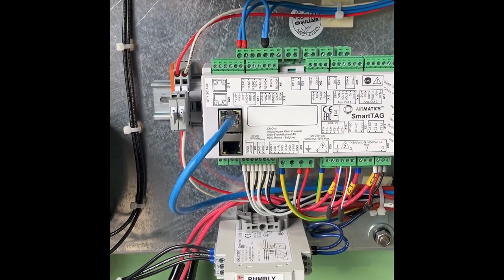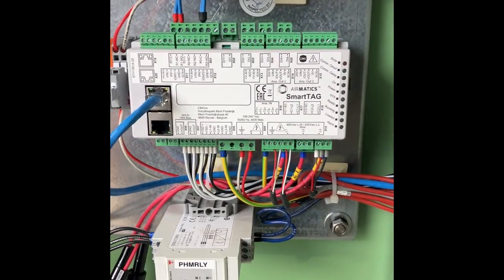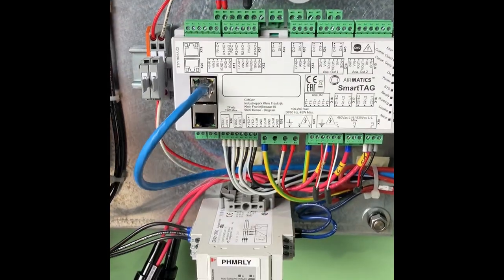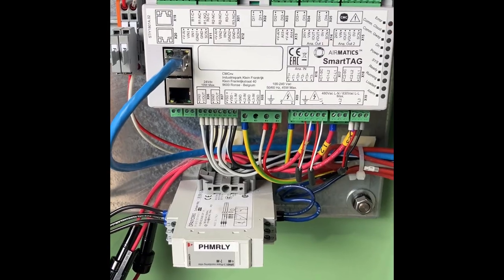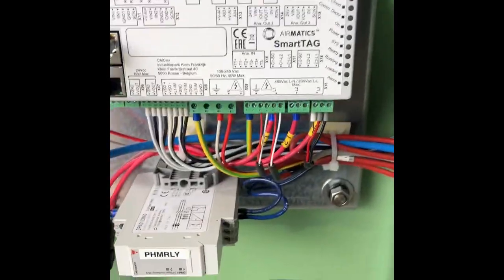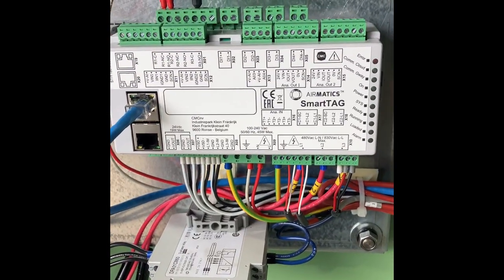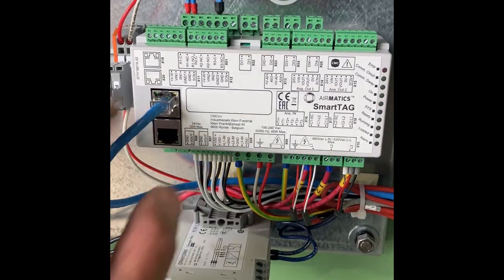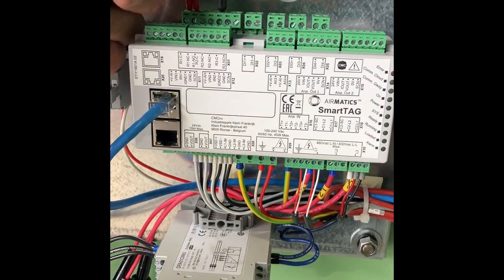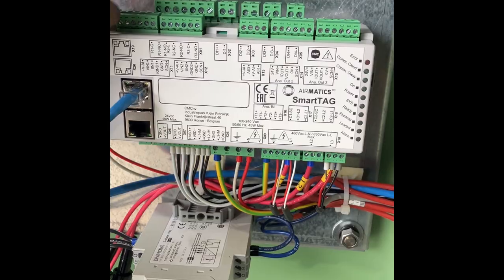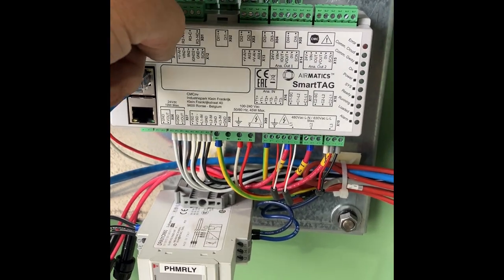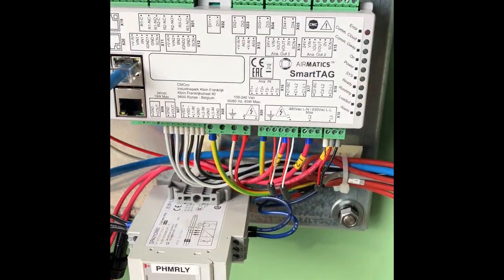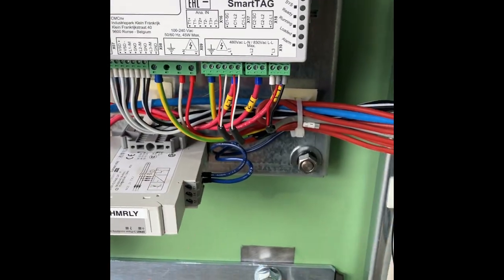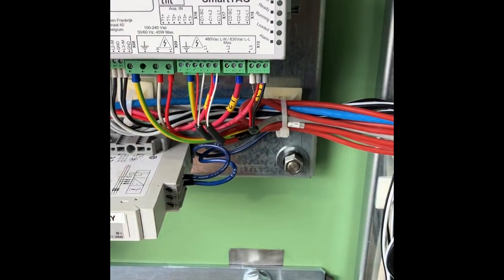Well, there we have it, compressed air friends. This SmartTAG here is officially official. Really the only changes you'll notice from the last time you saw it is we now have our digital wires up here. We got our 24 volts in, and we got our signal out for the remote unload, and we now have our Modbus wires hooked up here.